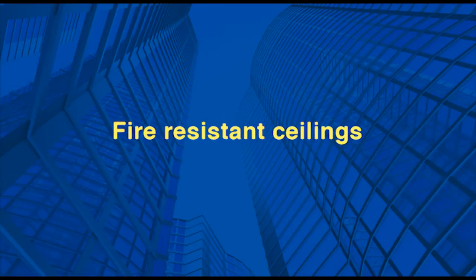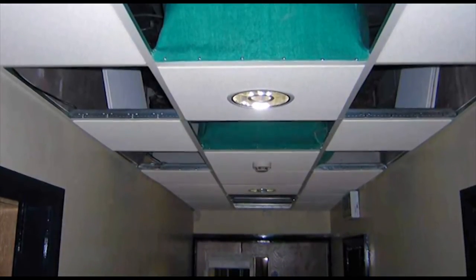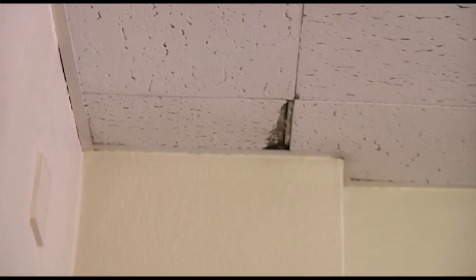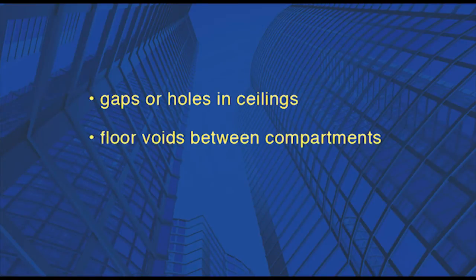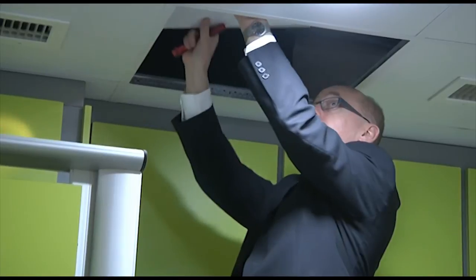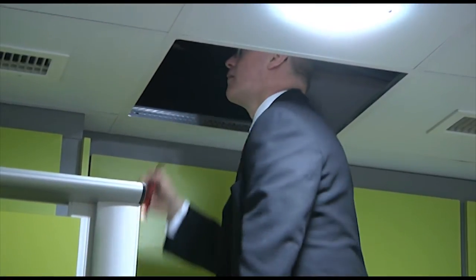Checking ceilings is important, as it is easy for ceilings to be downgraded from the original intended fire rating, for example by fitting untested down lighters. If ceiling tiles are damaged, they need to be replaced with the correct type, as replacement with tiles from another manufacturer can lead to premature failure in a fire. Other common faults include gaps or holes in ceilings, floor voids between compartments, and hold-down clips removed and not replaced following maintenance work behind the ceiling.